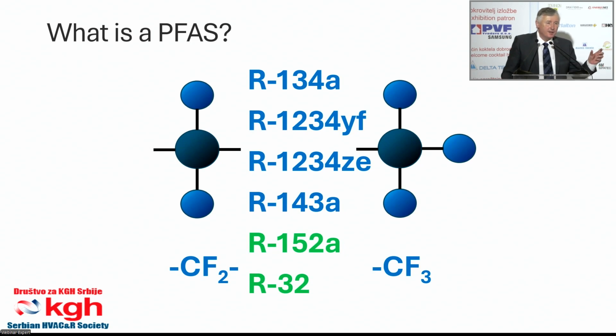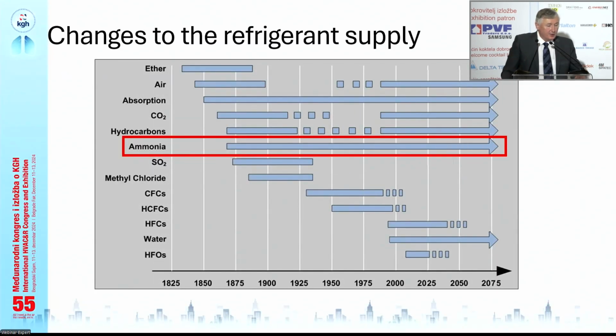But you need to bear in mind that these numbers have a very wide tolerance. So if it's 140 plus or minus 20%, or it's 770 plus or minus 20%, having a fixed number threshold doesn't actually make an awful lot of sense. Better to get right down to very low GWP. And some changes to the refrigerant supply. Again, I spoke briefly about this yesterday, but I want to highlight a couple of things. I'm talking about the phase out of HFCs and possibly HFOs as well. On the other hand, you can see some of these refrigerants will be available in the long term into the future.